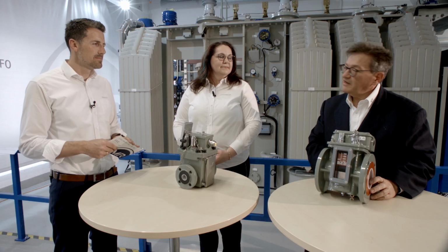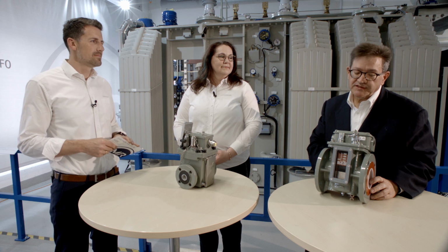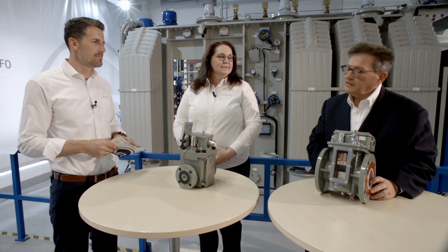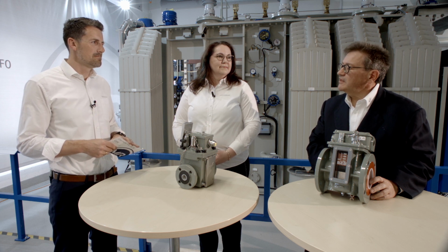The RR type Buchholz Relay from ETI CEDASPE can be equipped with a maximum of 6 switches. You can have 2 switches for the alarm top float, 2 independent switches for the bottom tripping float, and also 2 separate switches for the flow vane.